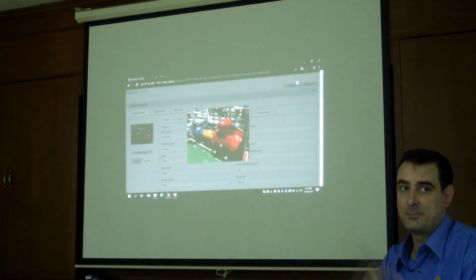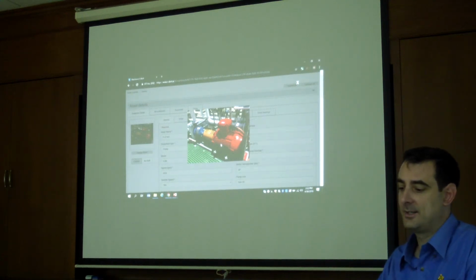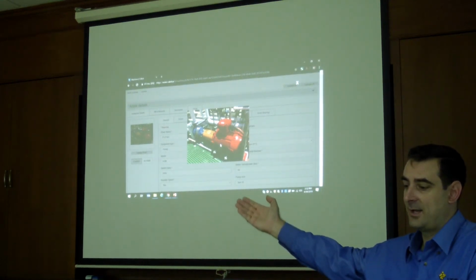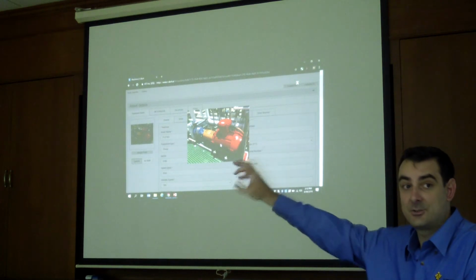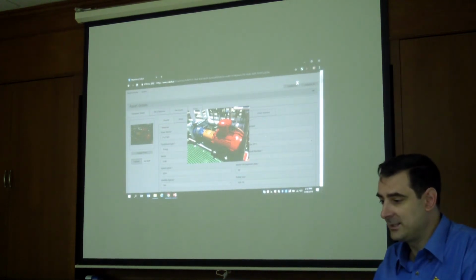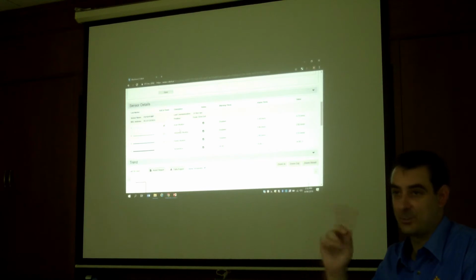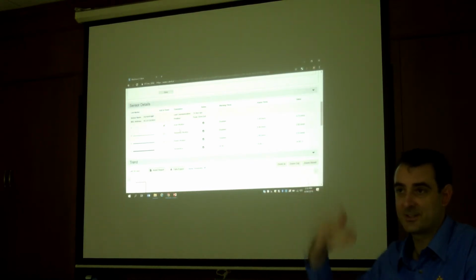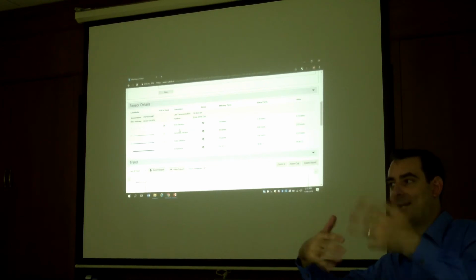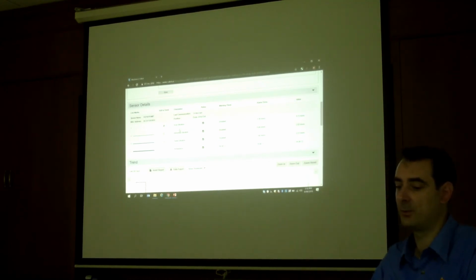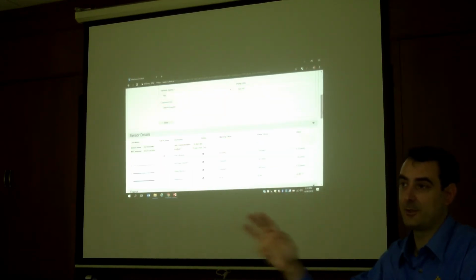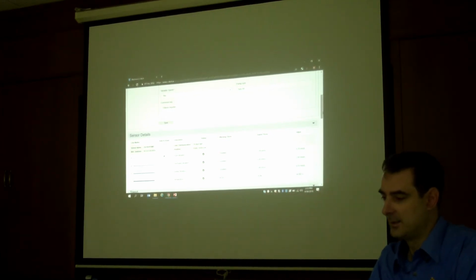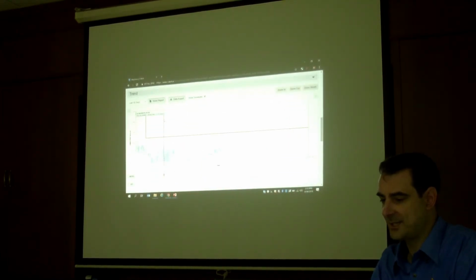So it's important when we set up with customers that we understand that that is the asset, and every sensor that goes on there is assigned to that asset. This gives you the ability to have multiple sensors on one equipment. This particular equipment only has one, but sometimes you'll have 2 sensors, 3 sensors, and then you can have all the graphs from one asset on top of each other. Works very well. Actually, one customer has 3: one on a pump, a gearbox, and the motor. That's one asset, but 3 sensors. So here, we can see the trend, but I know they have problems in the horizontal.